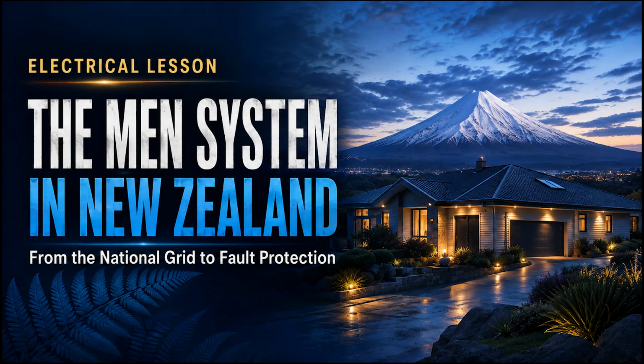If active touches the case, the protective earth changes from a normally non-current carrying safety conductor into a fault current conductor. It carries the fault to the earth bar, through the MEN link, and back by the supply neutral to the transformer. The protective device disconnects the supply. That is the complete story from the national grid to the appliance case. The large power system delivers energy. The MEN earthing system controls the consequences of a fault inside the installation.